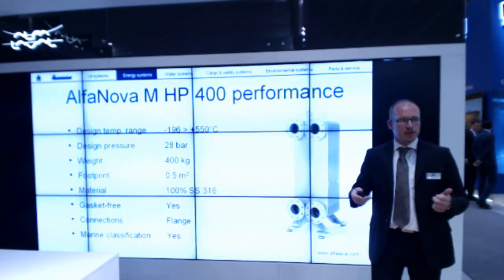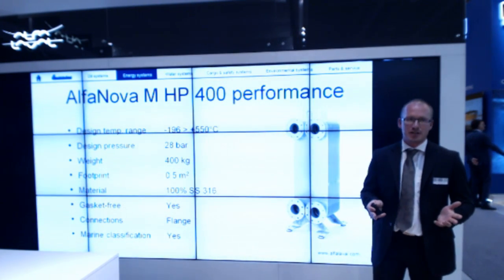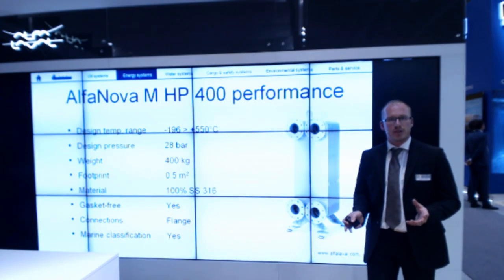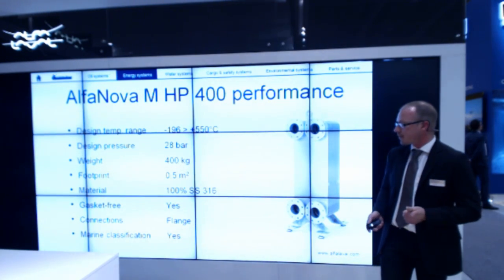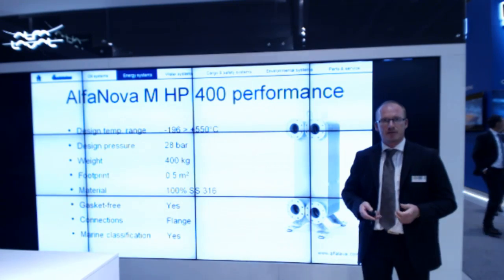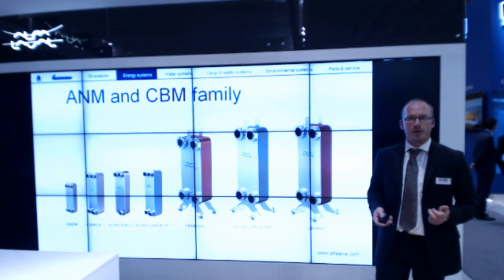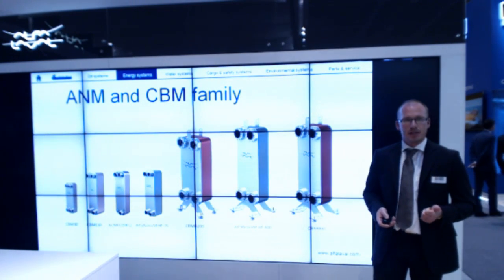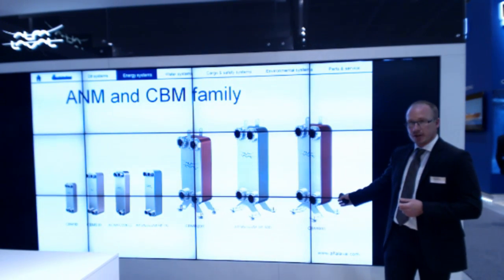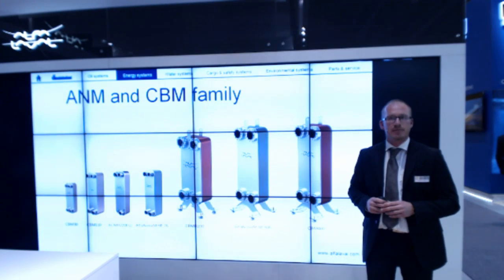In brief, the Alfa Nova covers a temperature range from minus 196 up to 550°C, covering most applications, with a pressure rating of 28 bar. It's 100% stainless steel with no copper, meaning it can handle media such as ammonia. It is delivered with marine classification. Furthermore, we have a full family of Alfa Nova and CBM — a copper-brazed product — ranging from CBM 400 with 100 millimeter ports down to smaller CBM 30 and 25 millimeter units.